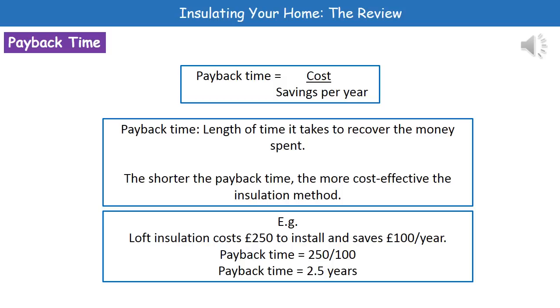For example, loft insulation costs £250 to install, and that will save £100 a year. So, to work out our payback time, all we've got to do is cost divided by savings per year: £250 divided by £100 gives us two and a half years to have made back our money. So, this one is a very cost effective installation method.